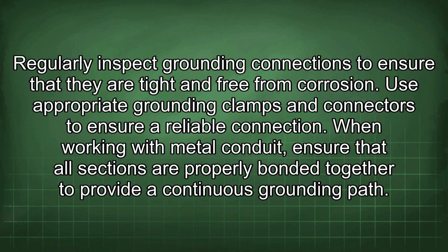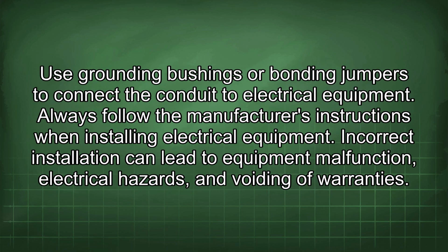When working with metal conduit, ensure that all sections are properly bonded together to provide a continuous grounding path. Use grounding bushings or bonding jumpers to connect the conduit to electrical equipment. Always follow the manufacturer's instructions when installing electrical equipment. Incorrect installation can lead to equipment malfunction, electrical hazards, and voiding of warranties.